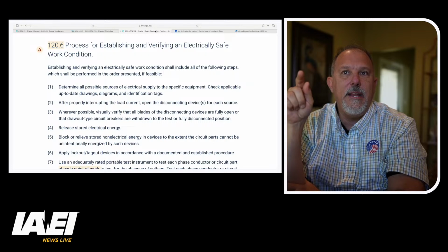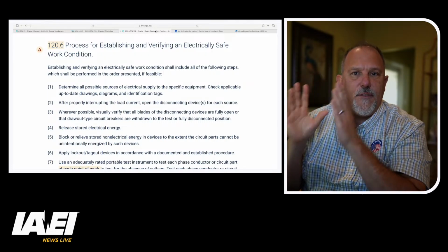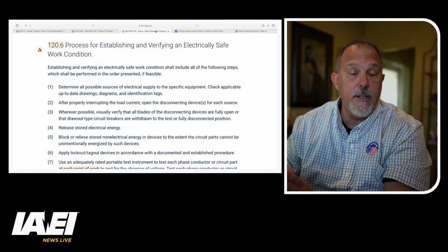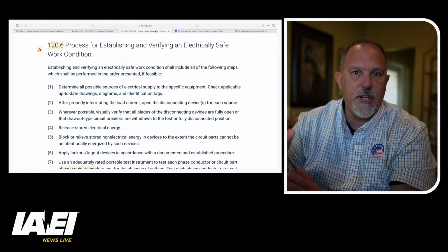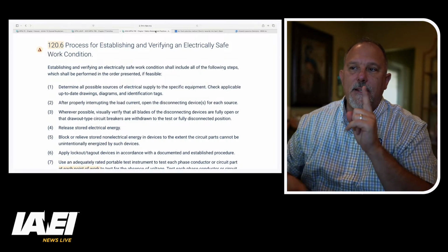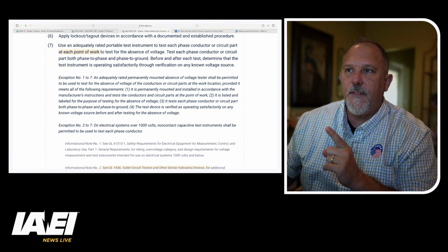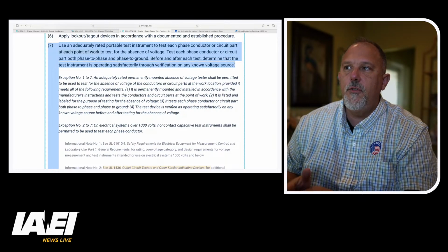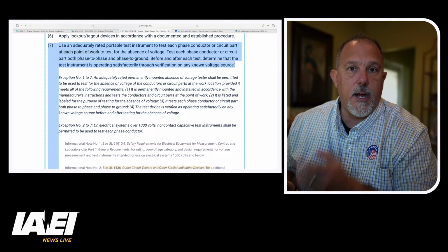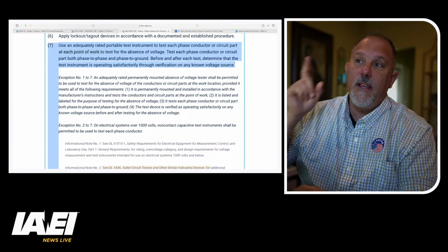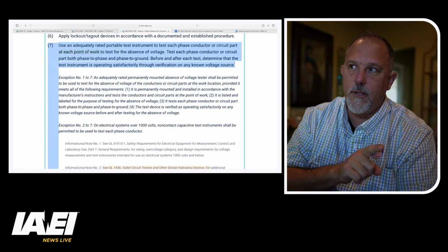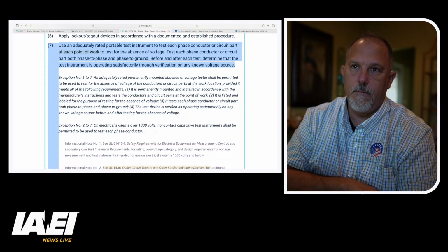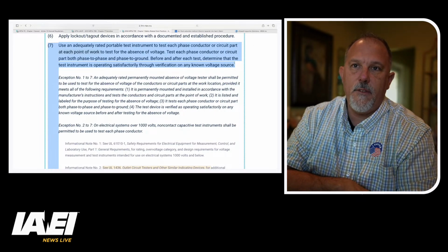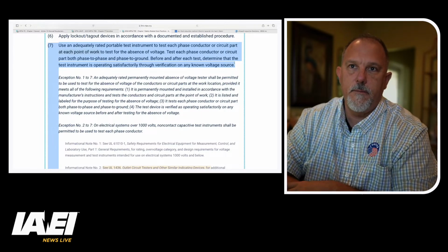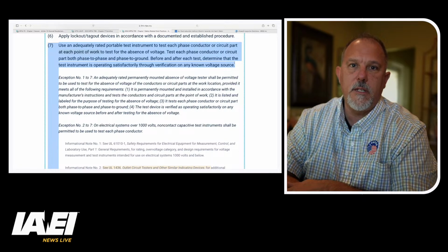If it is, then even that fusible disconnect switch which needs to be cleaned, while it is in an electrically safe work condition, that means that I have to, if I scroll down, if I consider item 7 to be energized work until I verified it is not energized, if I consider item 7 to be energized work, can I say that on that non-fused disconnect with the infrared windows, no work would be conducted while energized?